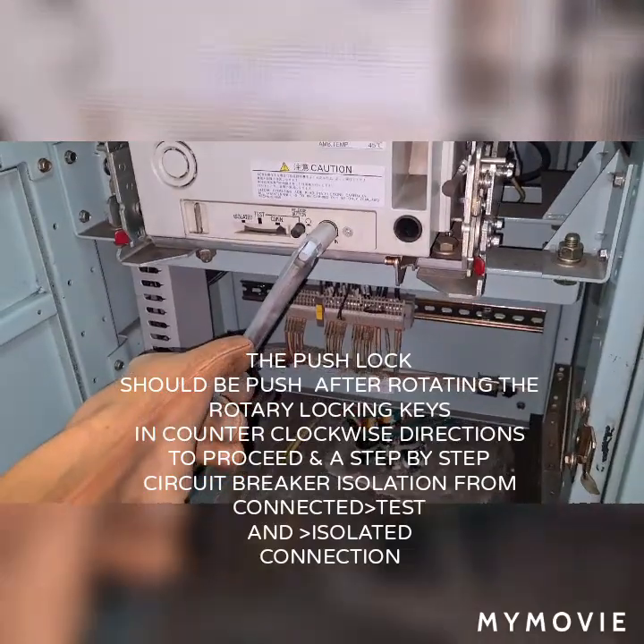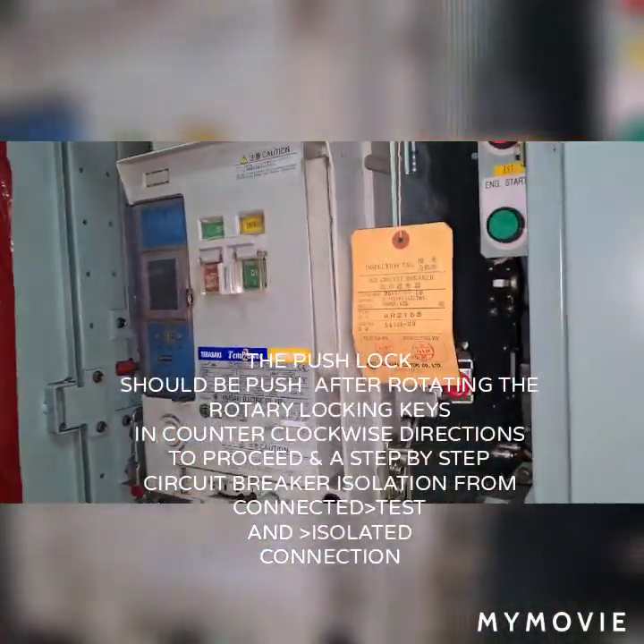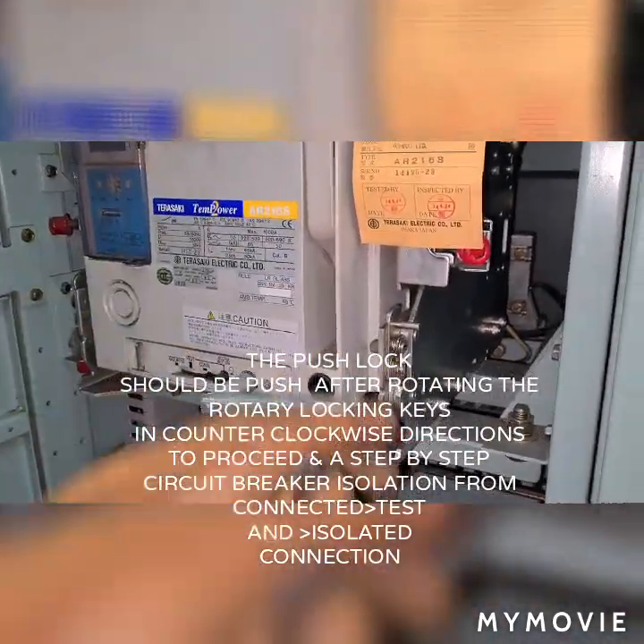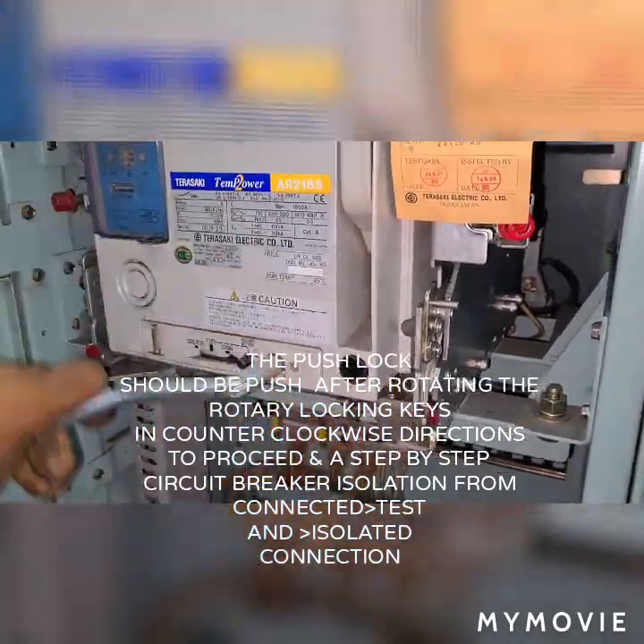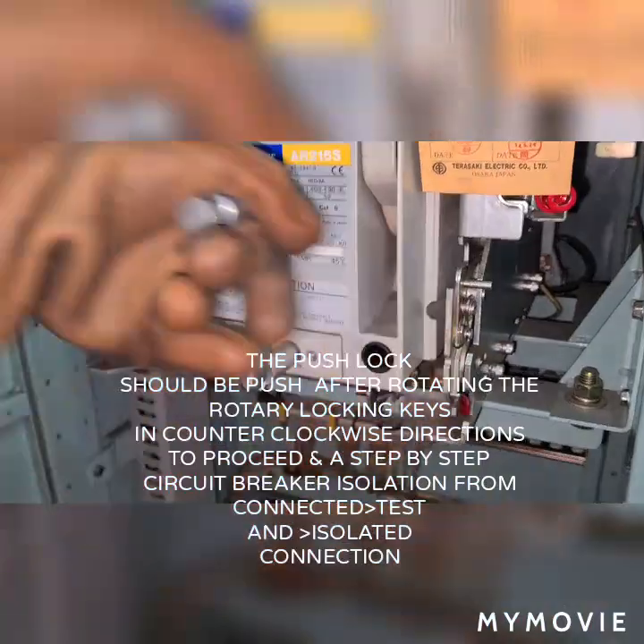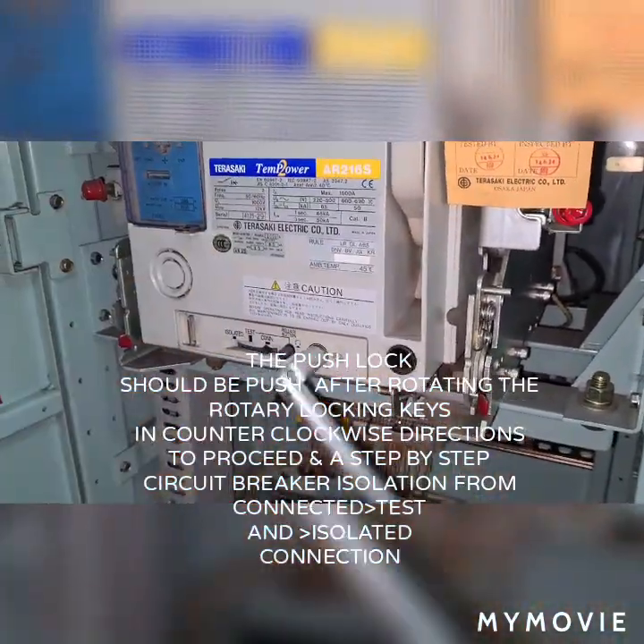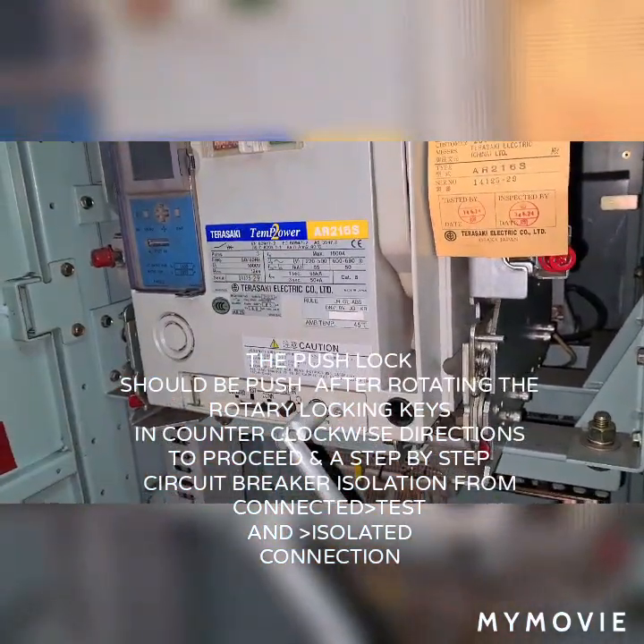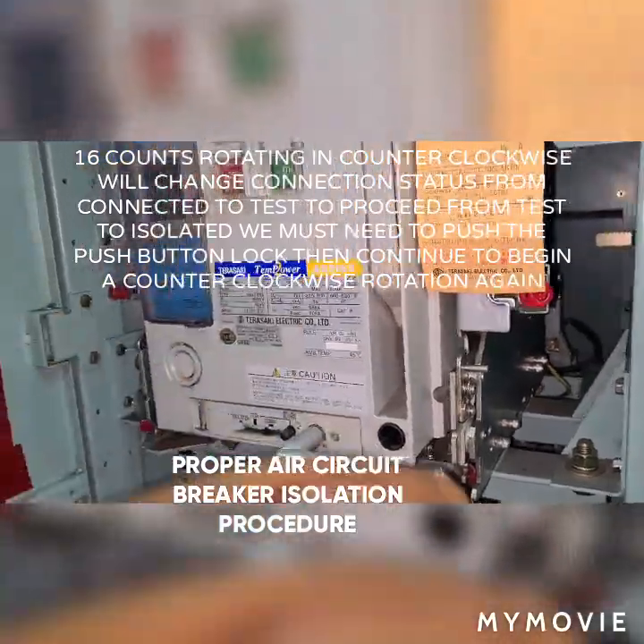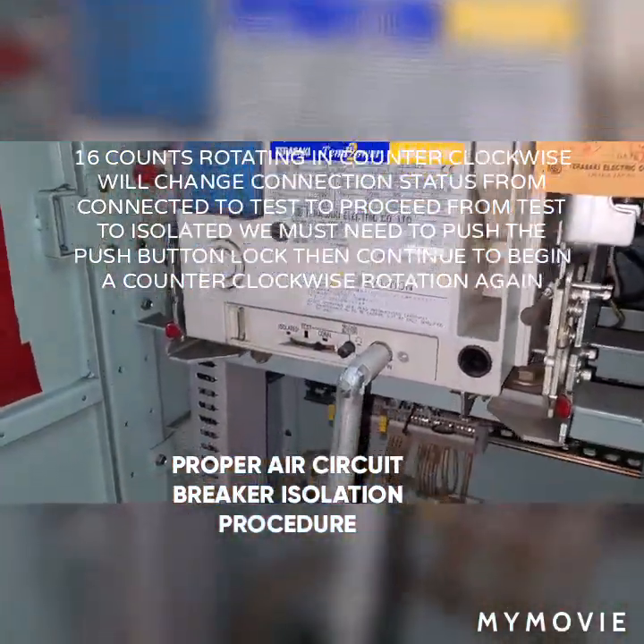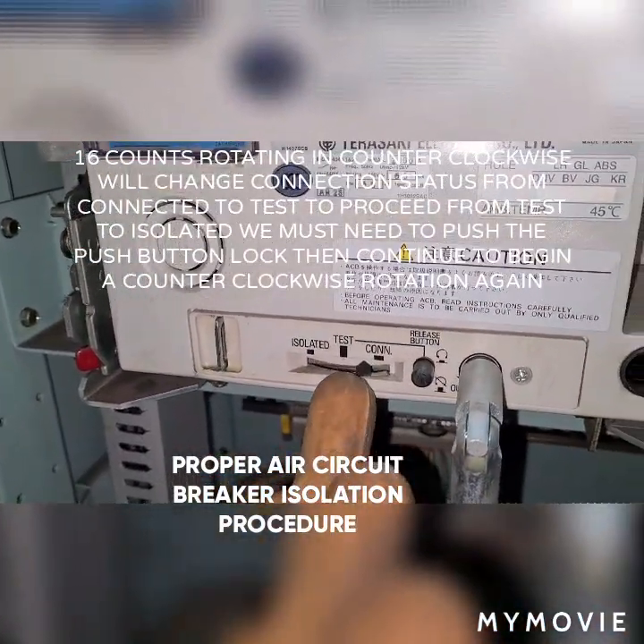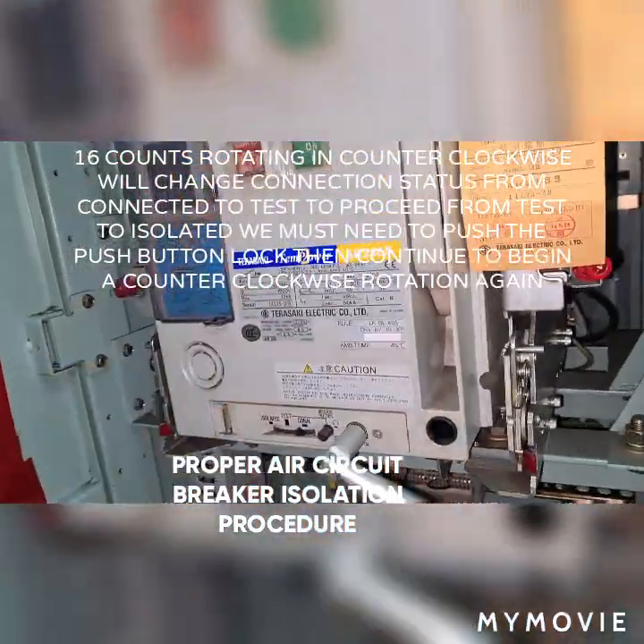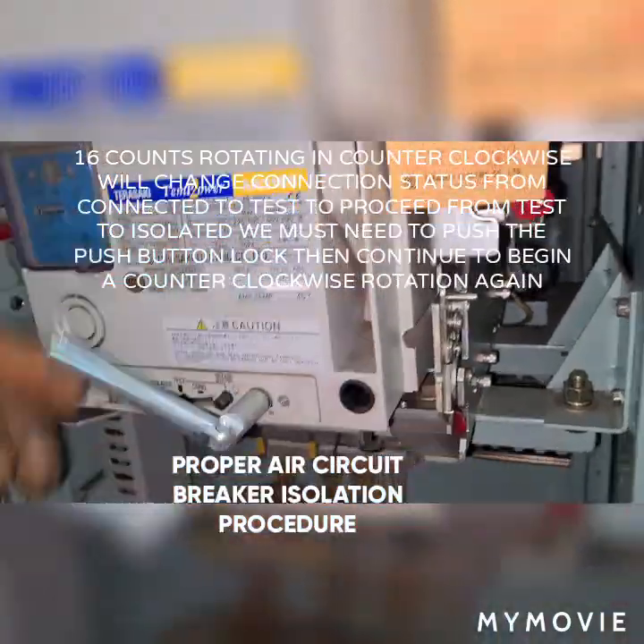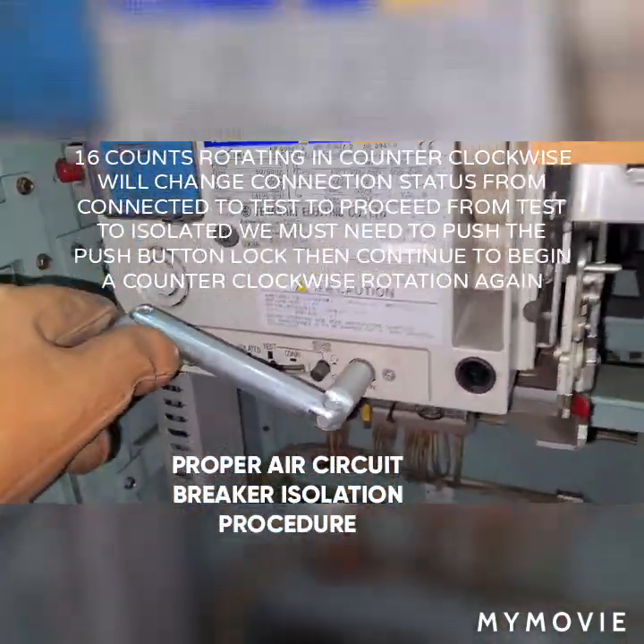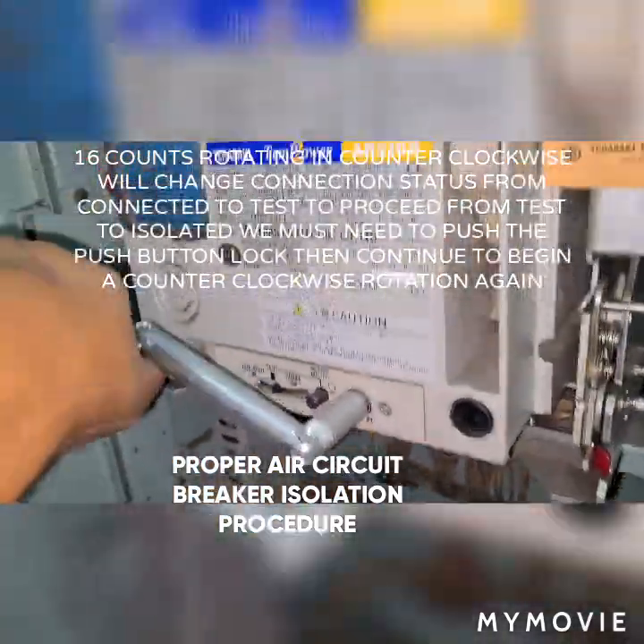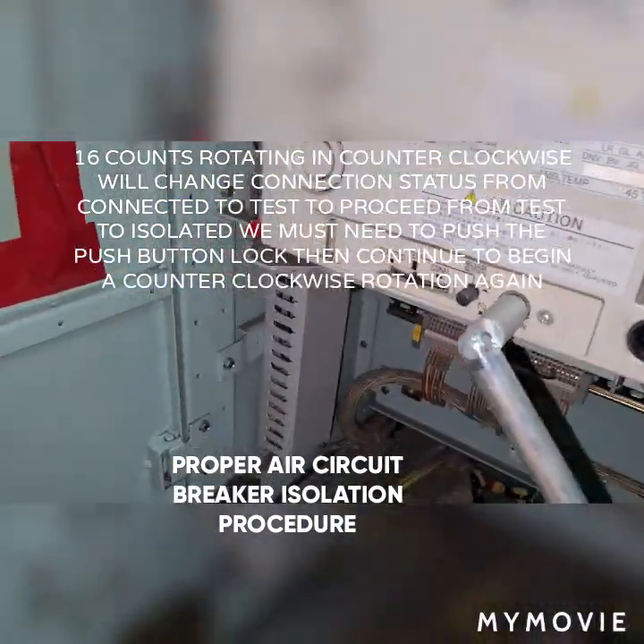Now I just inserted the key switch in the insertion hole, and this key switch needs to be rotated counterclockwise. As you will observe, after rotating it about 16 turns, the connection setting will change from connected to test, and we need to push the push pin and then continue to rotate again, so we will change the connection setting from test to isolated. That is how we isolate the circuit breaker and start to pull out or drawout the circuit breaker before doing any electrical maintenance work on the alternator.